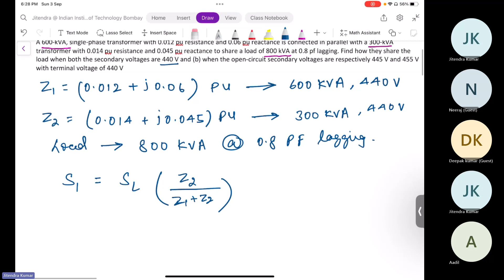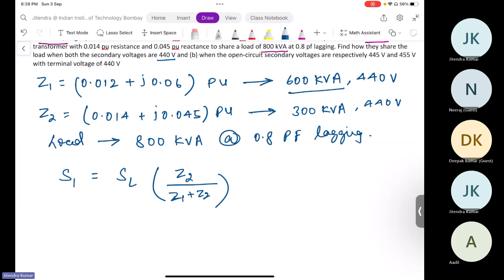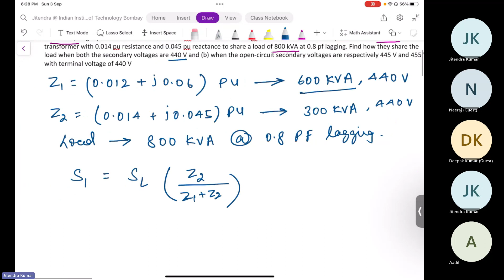But we have given the impedance values in per unit, and we want to simplify this problem with per unit only, but we have to bring them to the same base level of impedance. So I would like to convert Z2 with the base of Z1, because it has the higher rating of 600 kVA. To convert Z2's per unit impedance in terms of the base value of Z1, we have a certain formula.